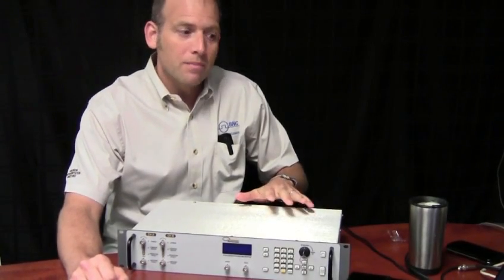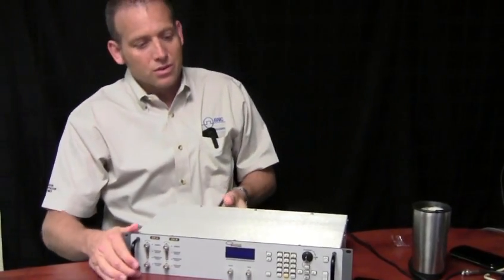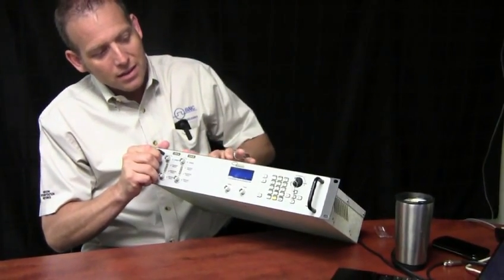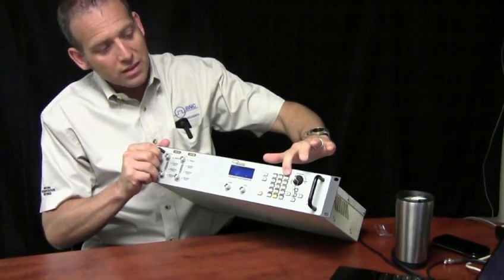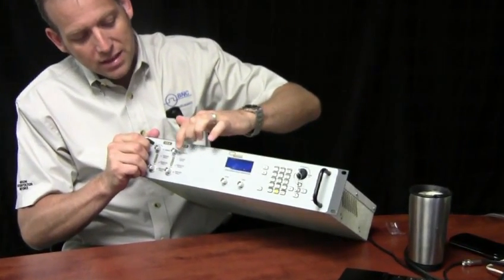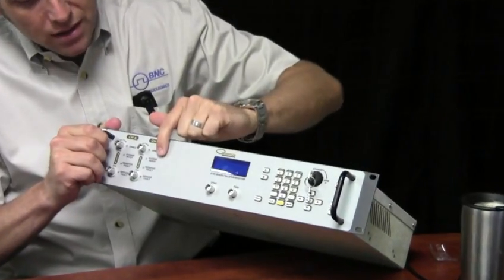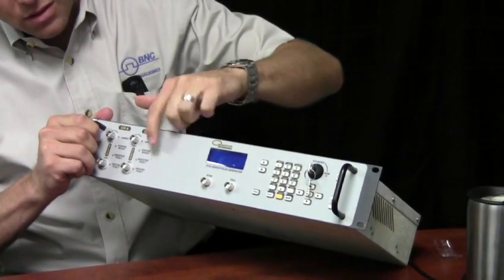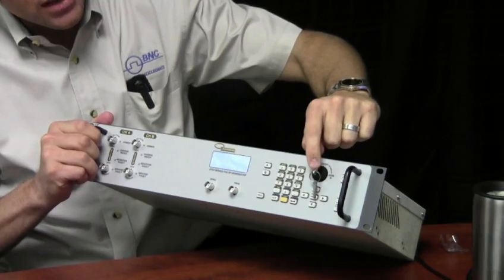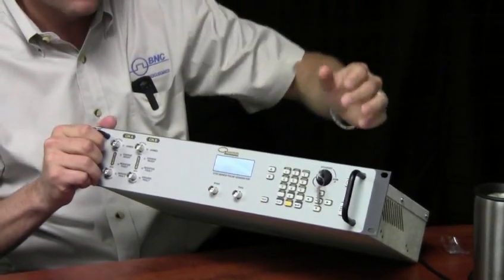We monitor the current and the voltage, and we give you front panel and rear panel sync outputs. The current generator is a convenient 19 inch rack, 2U height, with a user-friendly keypad interface and display. It gives you indicator LEDs showing whether each channel is armed, charge ready, resistor fault, or ground fault, and an additional power switch key which allows complete control by one user.